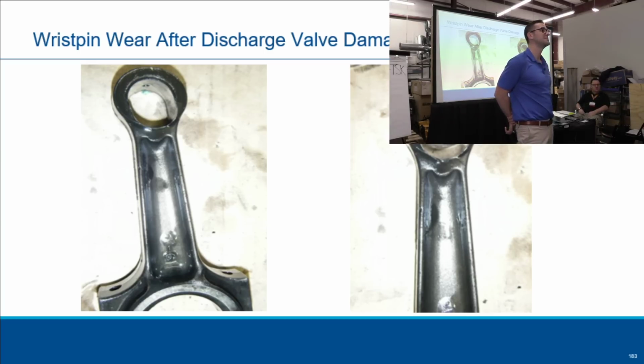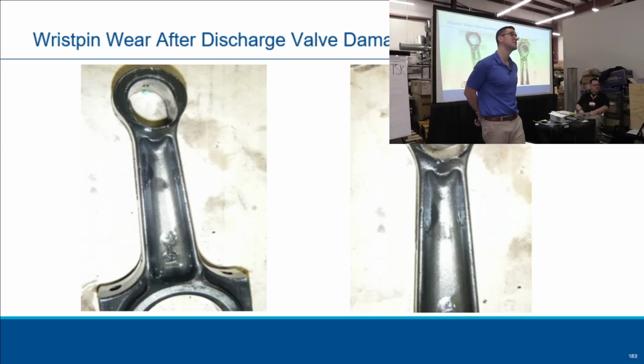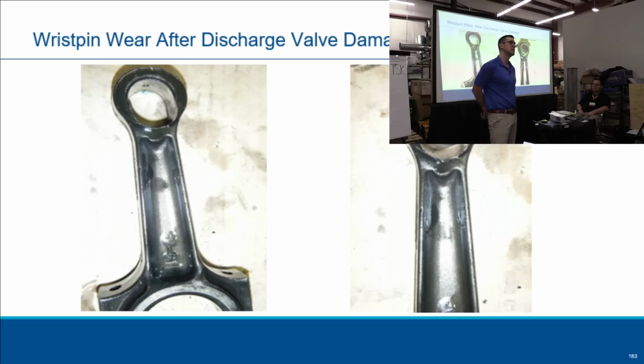Copeland Mobile. Go right to the amp draw. You put in your suction and your discharge, and then that's how you do it. That's how you check the valve plates. Doing the pump down test, Copeland doesn't recommend it. And like I said, I've done it on dozens and dozens of compressors to see if they hold. But if you do that example where the low pressure control and the unit just keeps running and running and running, and you know it's not a long run, well, there's probably something wrong with the valves.